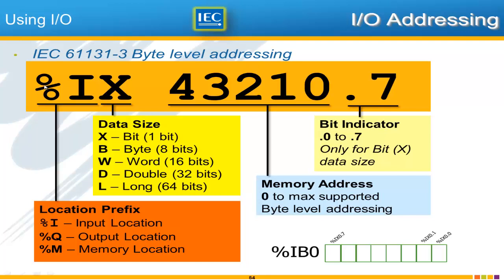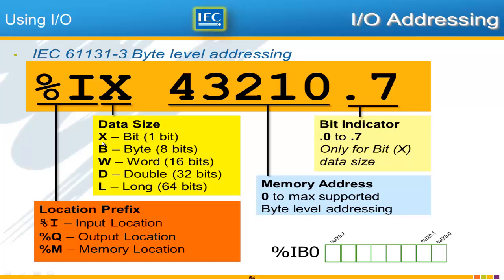I'd like to formally present the IEC 61131 byte level addressing. The first two characters are the % and a letter and that's called the location prefix. You'll typically see %I for input, %Q for output as I mentioned. And you may also see %M meaning just a memory location not particularly related to physical inputs or outputs.